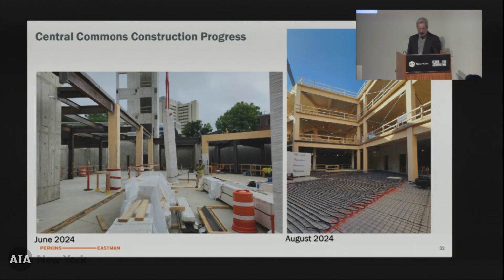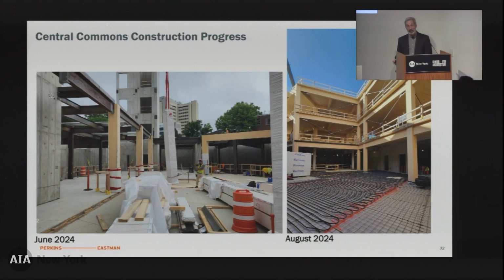A little more on the design progress here, where we're getting all of the systems in. The floor of that entire atrium is radiant heating by ground source heat pump—low temperature hot water, high temperature cooling. So this is a cooled radiant slab. When you come in the summer it'll feel comfortable and cool, and warm during the winter. It has to be coordinated—you can't just drill through that.